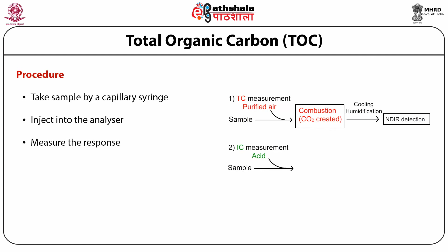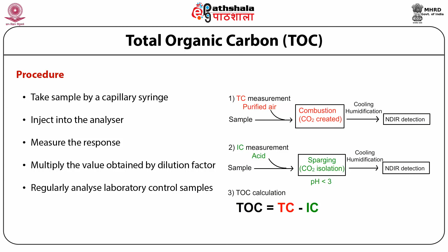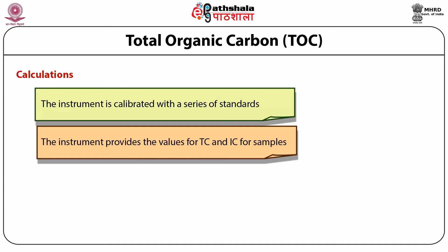Measure the response and repeat with three such estimations to obtain an average. Multiply the value obtained by the dilution factor if applicable, and then regularly analyze a laboratory control sample and standard to confirm the performance of the analyzer. The sample should lie within the range of the calibration curve so that we can determine the amount of total carbon present in the sample. The calibration is done by the instrument with a series of standards of organic and inorganic carbon to cover the expected range. Then the instrument provides the values of total carbon and inorganic carbon for the sample. By these two values we can calculate the total organic carbon by subtraction and express the result in milligram per liter.